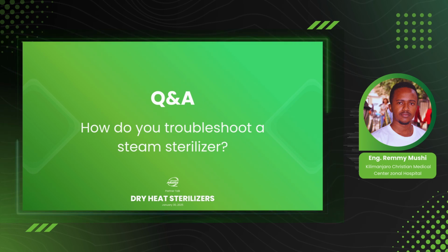Otherwise, if the pressure inside the chamber drops even by 1 bar or 0.5 bar, it means the heating element inside the boiler cannot perform at maximum load, or the material of that element is not the one that was supposed to be used, because you can have an element of the same wattage, meaning the same voltage, resistance and current, but you may find that the resistivity is different because of the material it is made of. So if you use a light duty heating element of the same wattage, it will not be able to heat the water inside the boiler to produce the steam in the required time.